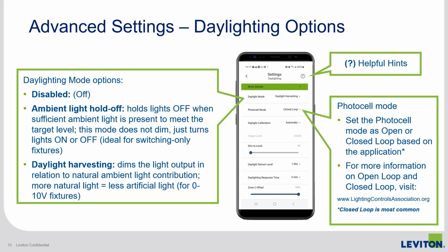The last is photocell mode. There are two options, open and closed loop. Closed loop is the default and most common way to measure lighting below the sensors and based on both natural and artificial lighting. Open loop is used for measuring natural lighting directly from a window or skylight.